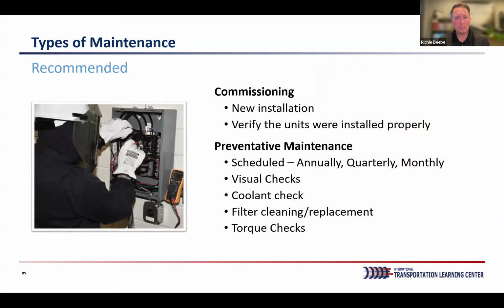Different types of maintenance. Commissioning. Over the past couple of years, we've really seen an uptick in commissioning, and that's due to more complicated installations, especially when it comes to DC fast chargers or level 3s. So what we do is verify that the installation was done properly according to the manufacturer specification.